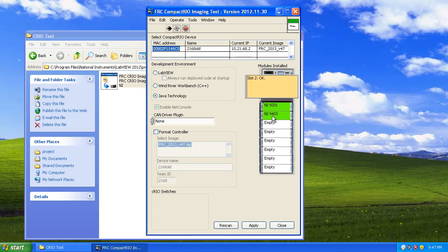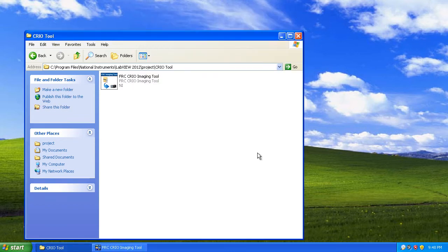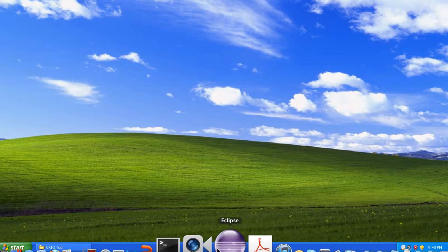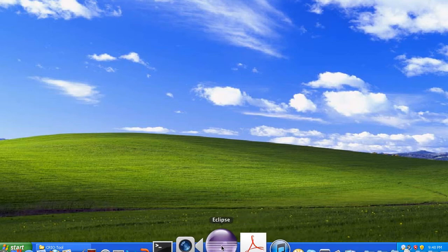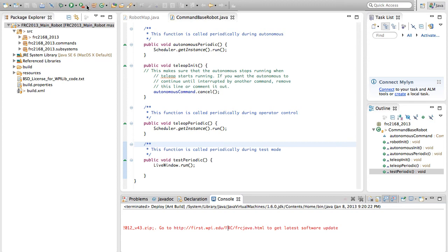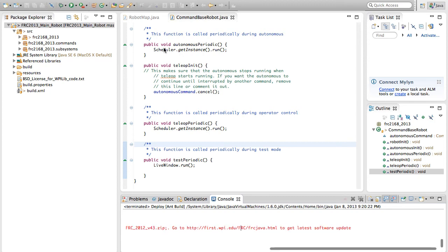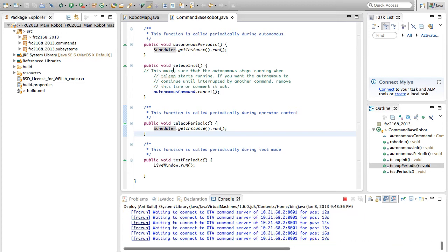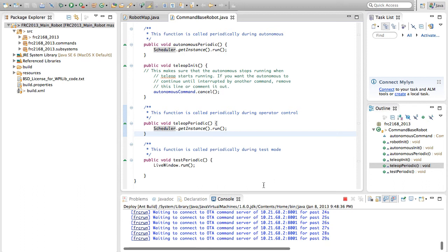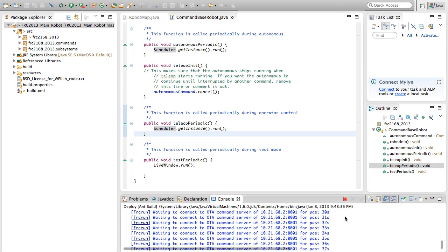I suggest you restart your CRIO before you try to deploy any code, or else you might run into a problem where you enter an infinite loop. I'll show you what that is. If I try to deploy this code now in Eclipse, you see I have to wait to connect to the OTA server for a very long time. That's because after you image a CRIO and you don't restart it, you run into this bug. It's a known bug. The fix is simply restarting your CRIO and then deploying again. I'm going to stop this, restart my CRIO manually, and then try and deploy again.